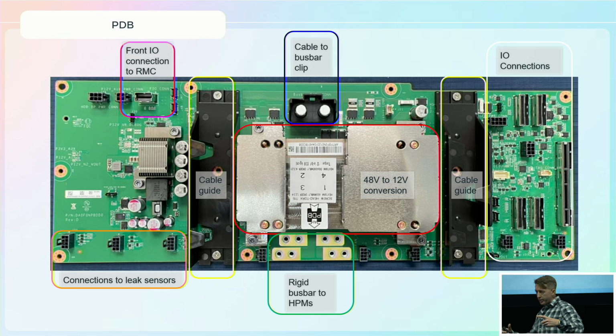Also within the tray, we have very granular, fast-acting leak detection. At the physical implementation level, you have rope sensors that are sensitive to liquid and change resistance when wet. That signal processing to detect whether the cable is getting wet is done on the PDB, along with a management and control CPLD used to both report and quickly act if there's a leak in the tray. It's tightly coupled to the power, so if there's an appropriate or catastrophic leak, it can very quickly shut down the tray with safety in mind.